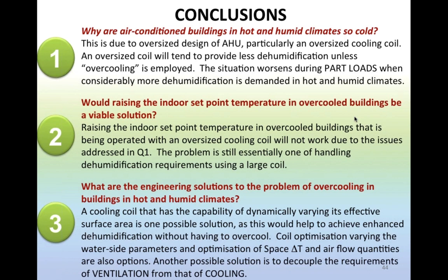Well, that's where I think there's a match or a balance needed between the expected loads on the air side, i.e. the cooling coil capacity, and what the chiller loads must be. So I fully agree with that point. An undersized coil, I don't think we want to undersize the coil. Rather, we want to translate that same level of flexibility we build into the cooling coil operation back up the chain into the chiller sequencing or chiller operation. So yes, that's why these challenges have kept us all in business, I guess, over the years.